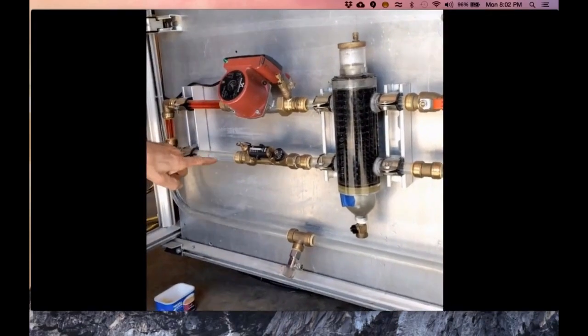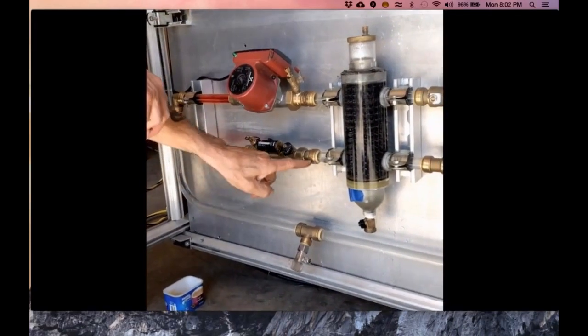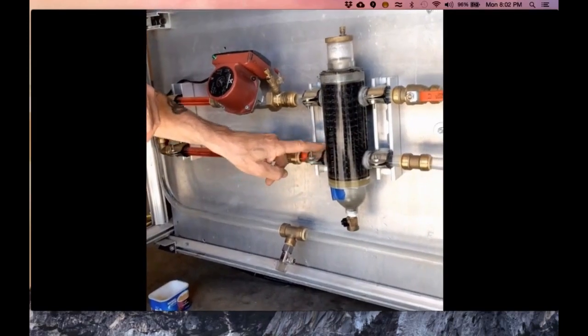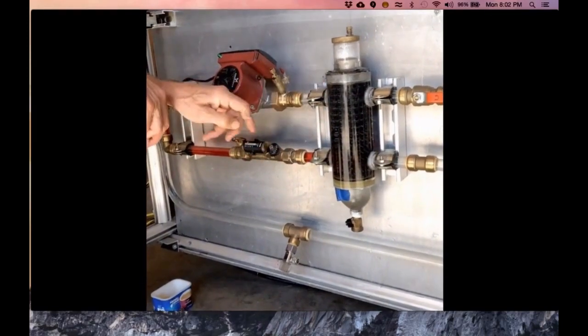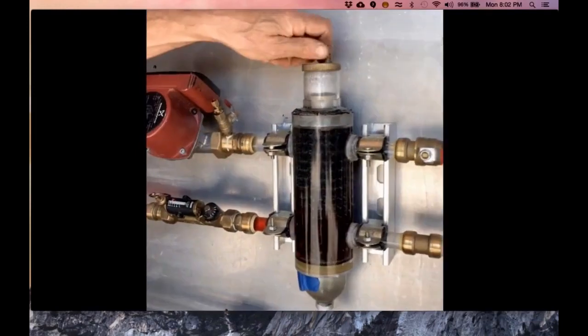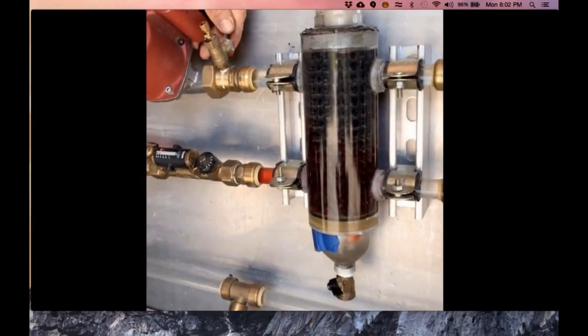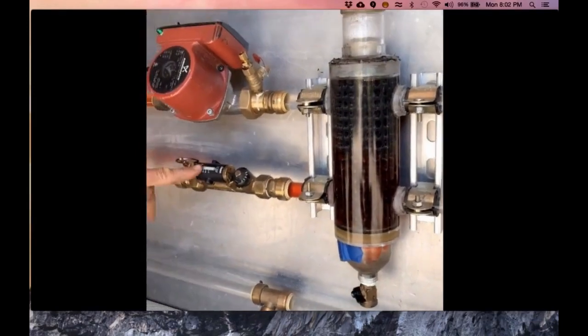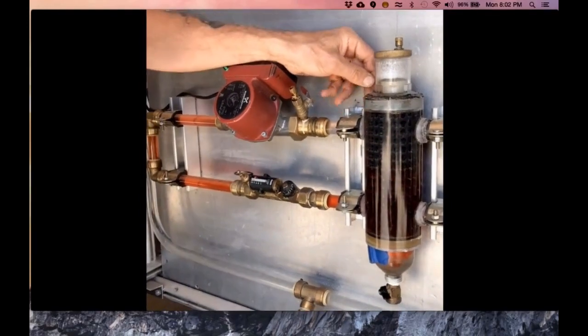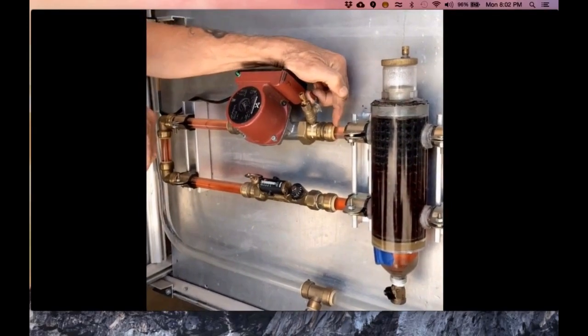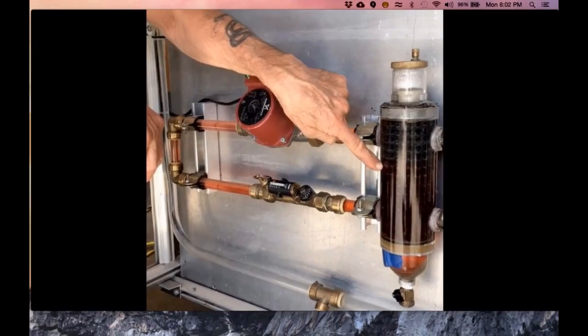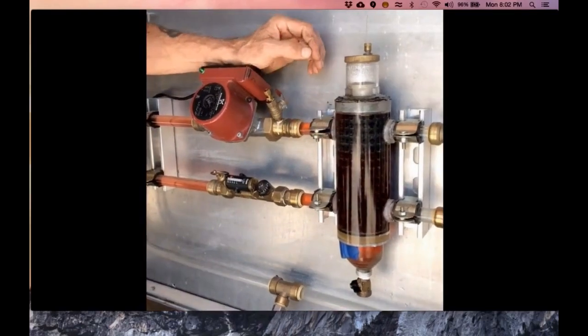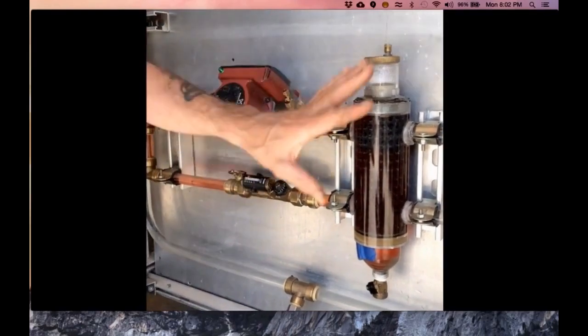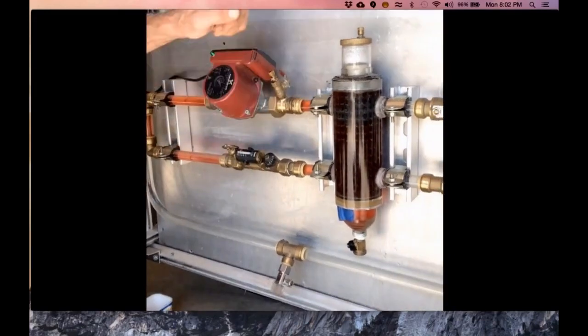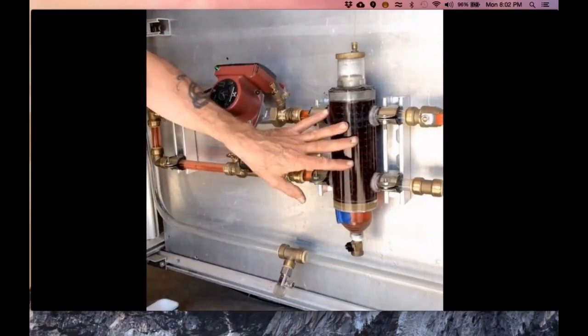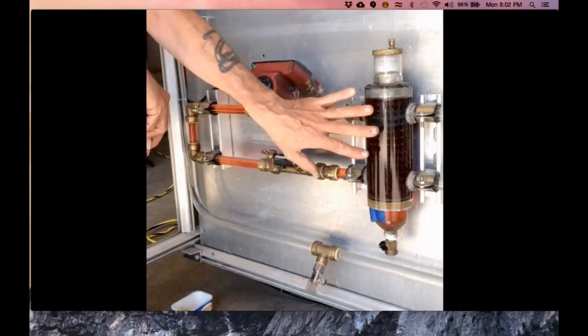See, almost immediately you can see that red color coming around. Coming into the separator. See it, but it's going right up the side there. Go back up to the top. I've got about 3 gallons a minute going through here. See the red just now starting to come through there as it makes its way up. You can kind of see it migrating up through there. Only got about 3 gallons a minute going through this, so I can have it nice and slow so you can see the air bubbles and everything coming out as we go. So that's this side here, and I could run that for hours, and that red will stay over here.